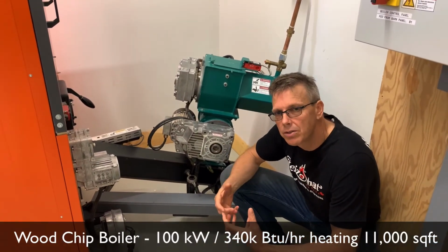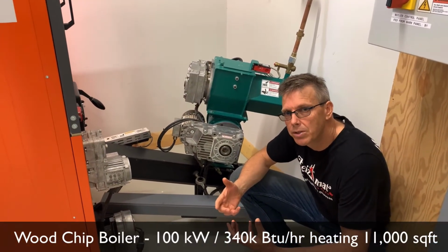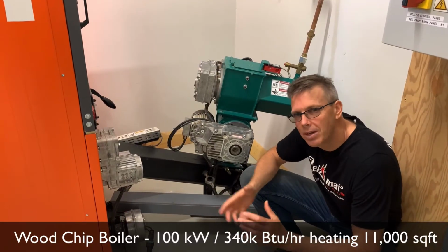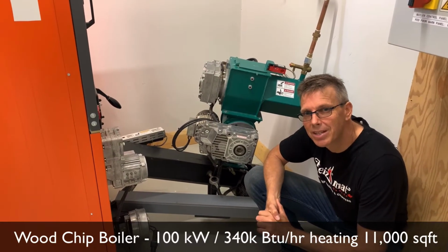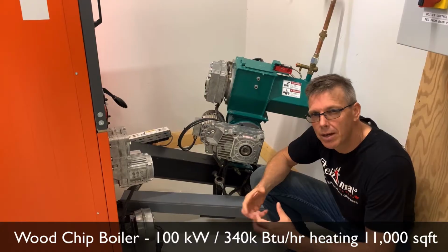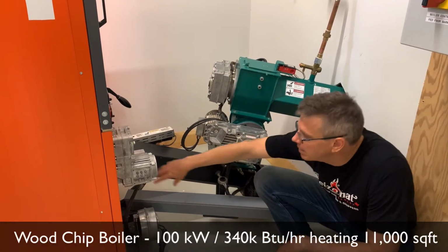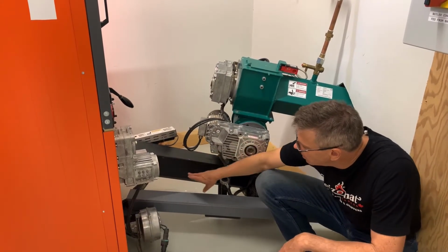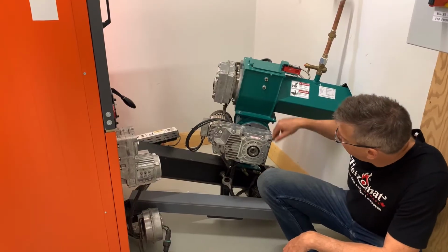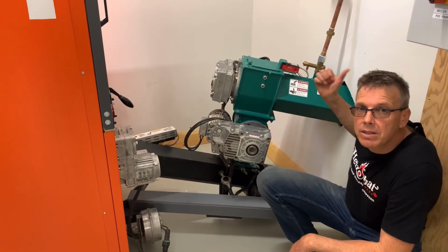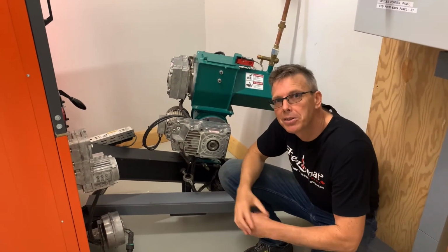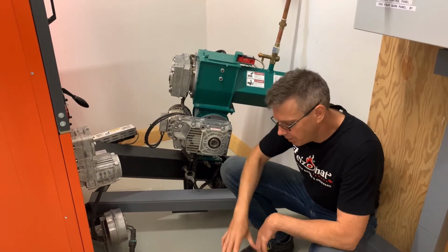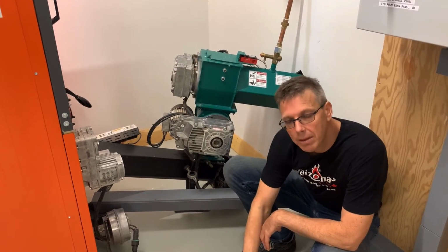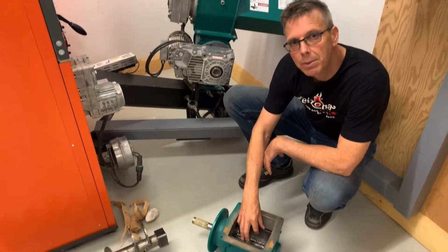In some cases, if the boiler did become positively pressurized, we have ways of monitoring that and making sure it doesn't happen. But in a worst case scenario, like a power cut, if fire lit the fuel in this auger, we definitely do not want it getting back into the bunker, because that would be a big disaster. So this is our primary way to block that, with a physical separation of metal blades.